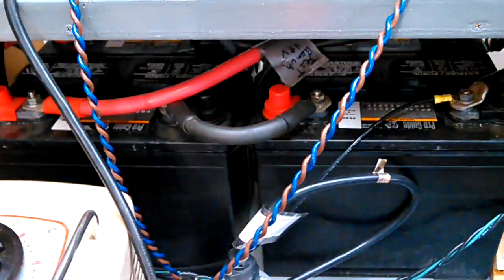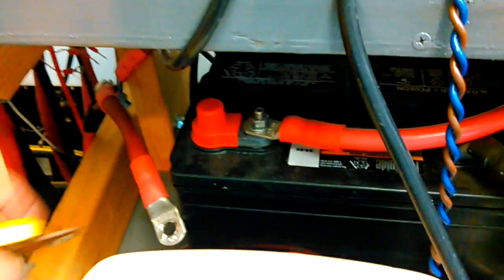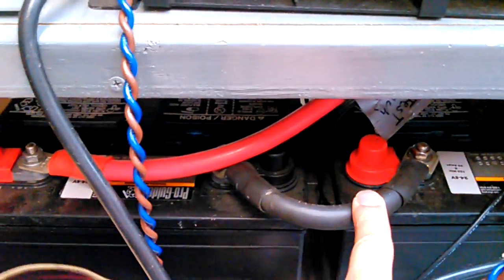So what's better, especially if you have a series parallel combination pack like this, is that instead of putting it on the one on the end where you have a feed out cable, put it in the middle here where your two batteries join together. Then this won't get as hot, because with a series parallel combination like I've got here with 4 batteries, this is going to be half the current of the feed-in wires. So this would be a better place to bolt it.